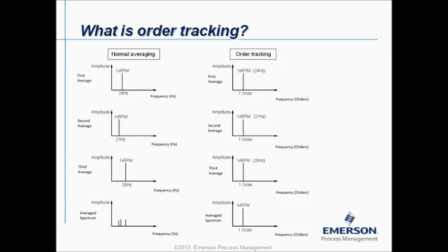In reality, this process will be repeated several times, and at the end an average spectrum will be stored. This is to have a good representation of the vibration data coming from the rotation of the machine in the final spectrum, and to eliminate random or one-time vibration sources.